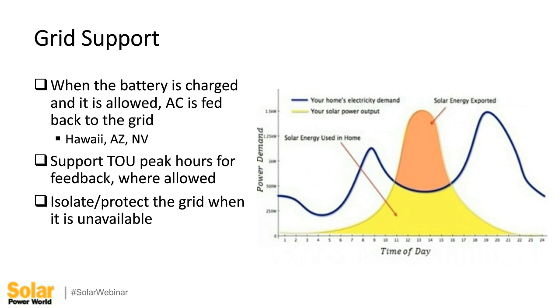Anymore, you really need a hybrid inverter that you use to support time of use peak hours for feedback. So if you've got peak hours, they used to be at 1 o'clock to 6 o'clock, or whatever your local peak was. Now you need to look at it because they're changing because of solar being added. It's now 5 o'clock to 8 o'clock. So you need a hybrid inverter that's going to be charged and store the power until its peak and then feed it back at that point. One, you'll get your better financial return, and two, you're actually complementing the utility and helping them out. We need to work on this together.